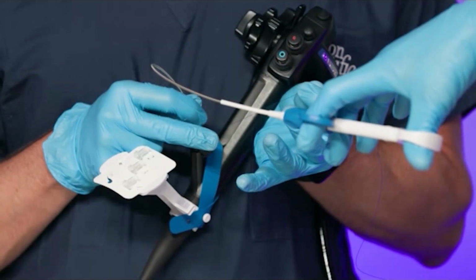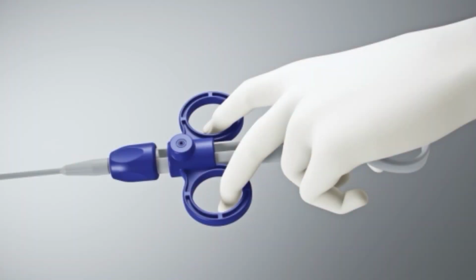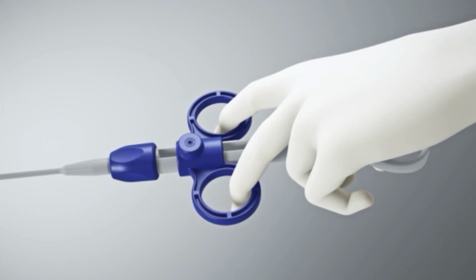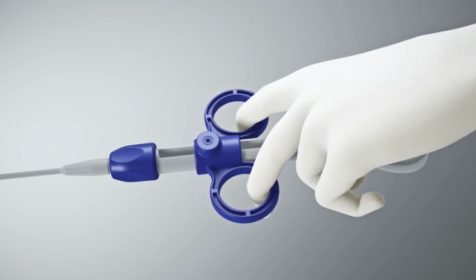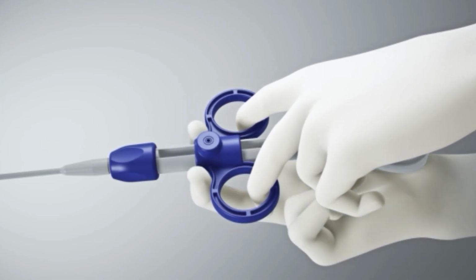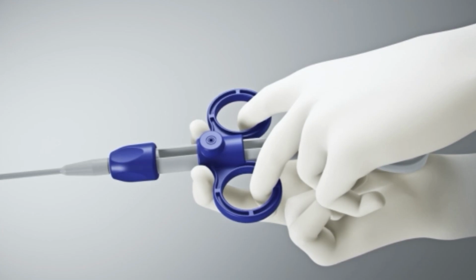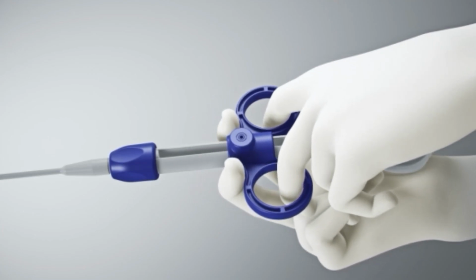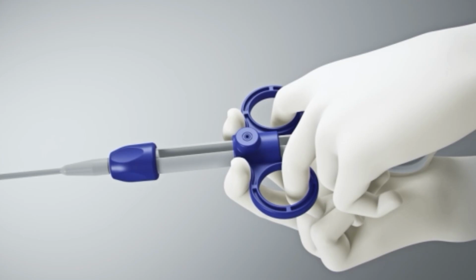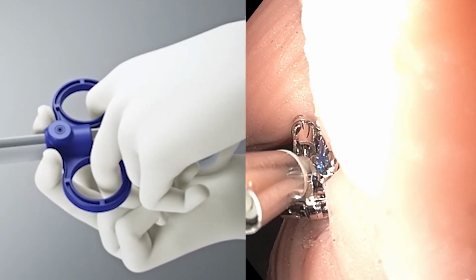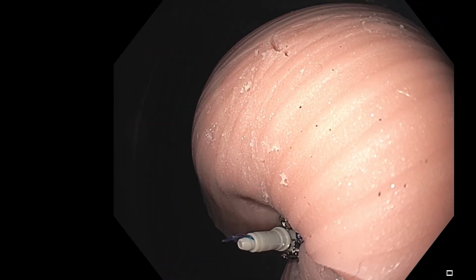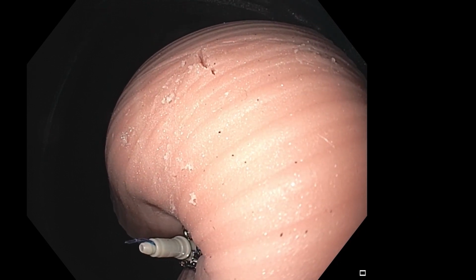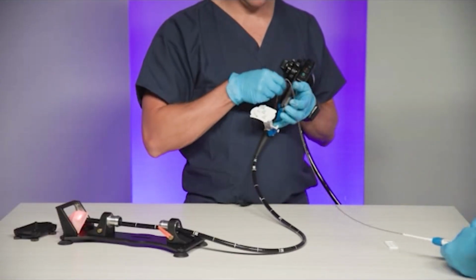Stage 1. Squeeze the cinch handle with one hand to pull the PEEK plug into the PEEK collar and lock the suture. Stage 2 of deploying the cinch will require 2 hands. Continue to squeeze the cinch handle to advance the beaded rod through the PEEK plug. Finally, continue to squeeze the handle to activate the suture cutter and release the PEEK collar and plug. Remove the cinch and remaining suture from the scope channel.